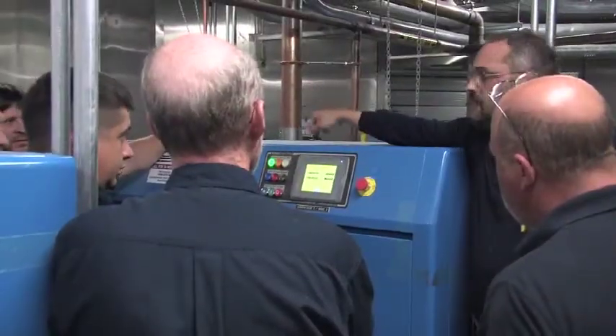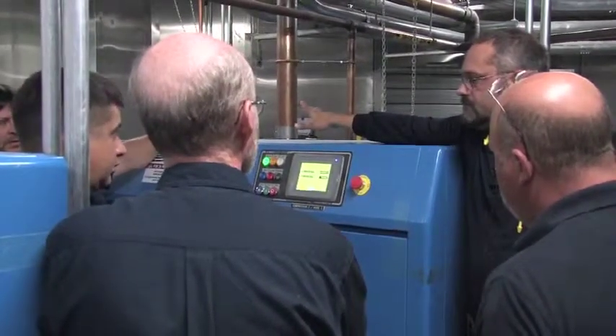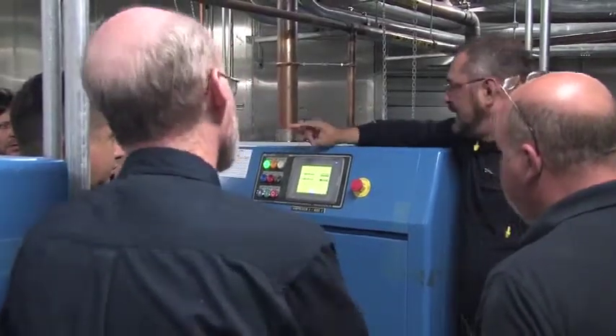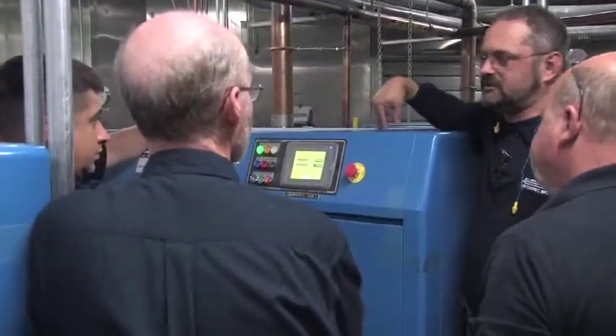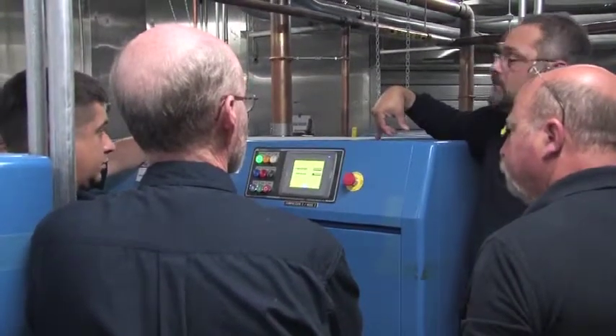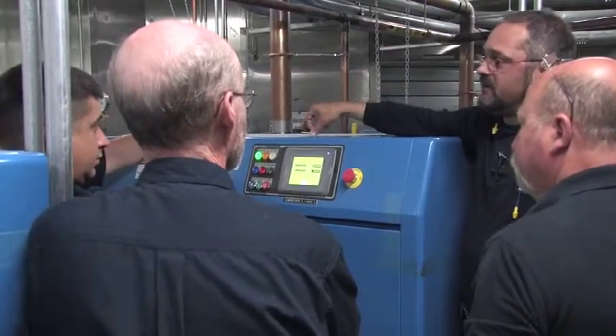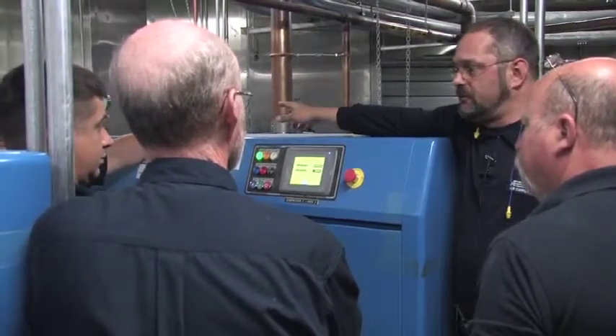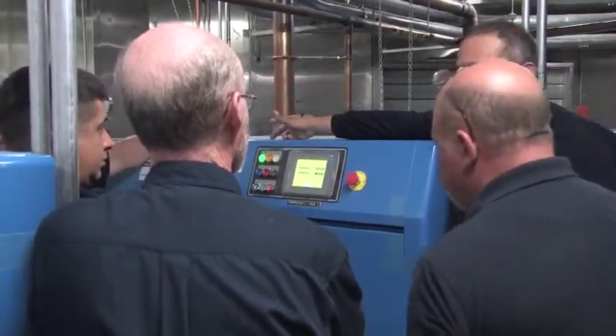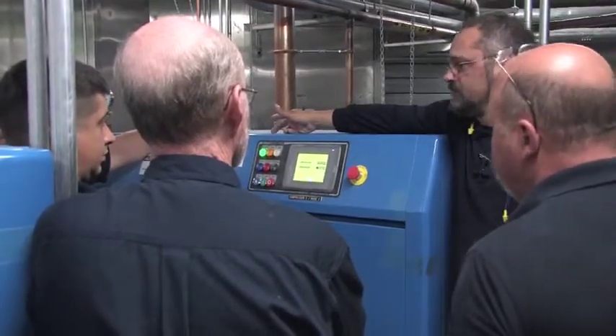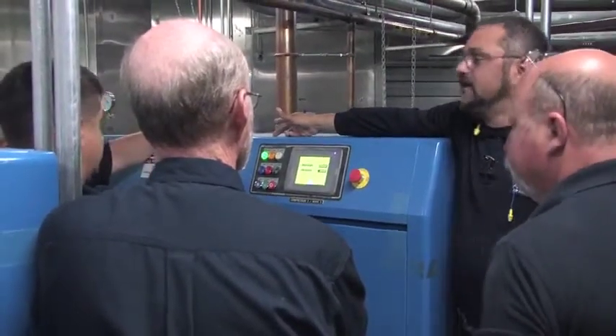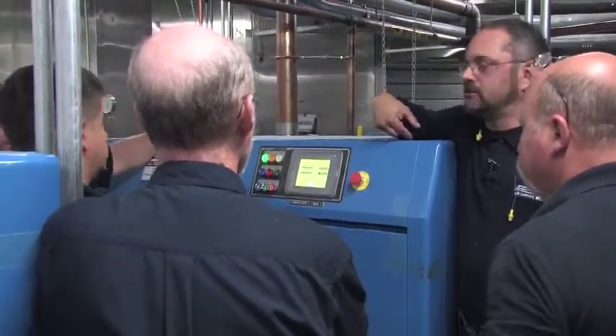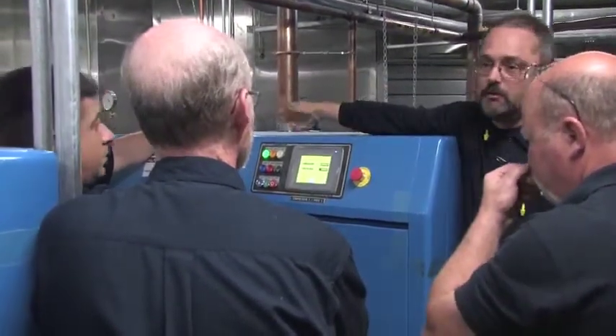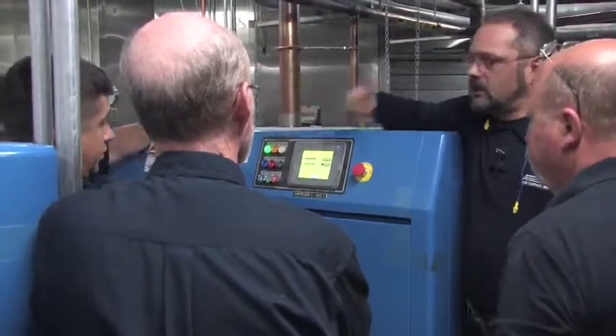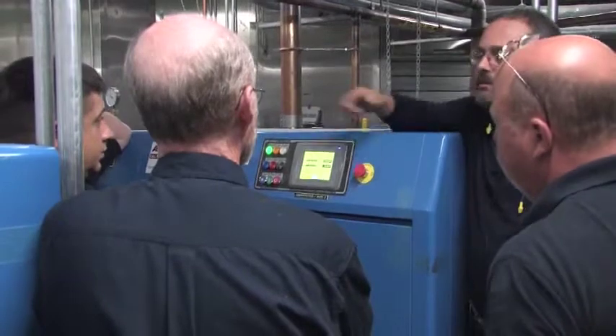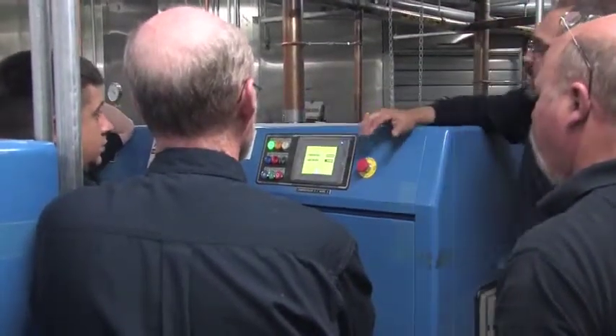Two things to remember. The temperature sensors are all identical. In other words, they're all interchangeable. If you've got a bad sensor in your second stage discharge, the machine won't run. But if you've got a good sensor on your first stage inlet, the loss of the inlet temperature sensor is not a shutdown condition. So you can steal that probe and put it to replace the defective one while you're waiting for another one to come, if you want to get the machine up and running. That's actually why they use all the temperature probes the same, because you can take the couple that aren't critical and swap them around.